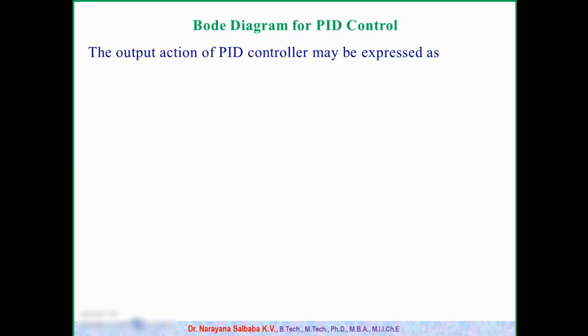If we use a proportional controller, it can minimize the error, but it cannot completely eliminate the error. In a proportional controller, there will always be a steady state error, which we call offset. To eliminate the offset, we add an integral element to the proportional controller. This integral element eliminates the offset and brings the control variable to the required value, so the error will be 0. But at the same time, the integral element introduces some oscillations.